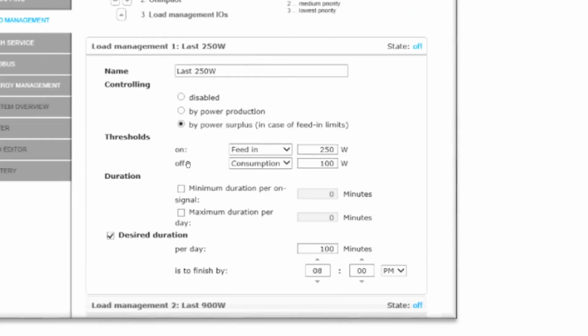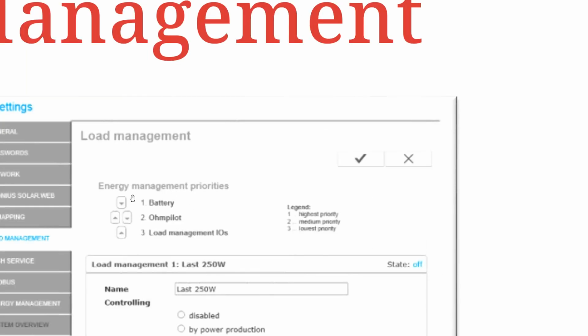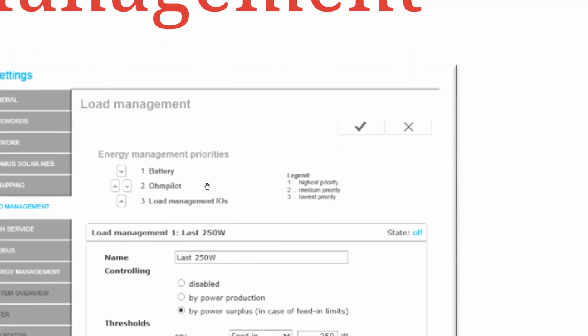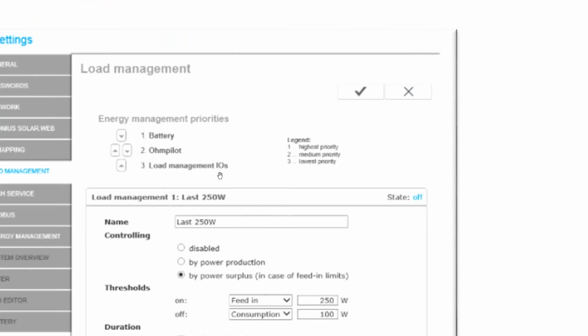It's very, very important also to do the energy management priorities or prioritization. So here we can see that we have the possibility to prioritize from the battery to the Ohmpilot and then the load management IOs. And as we can see here, the description of the legend, it says here that number 1 has the highest priority, number 2 is medium priority, and number 3 has the lowest priority. So what basically this means is that when you have the battery as the number 1 priority, any available surplus energy will go to the battery first.